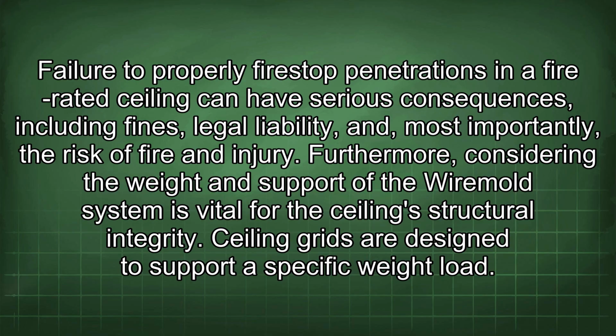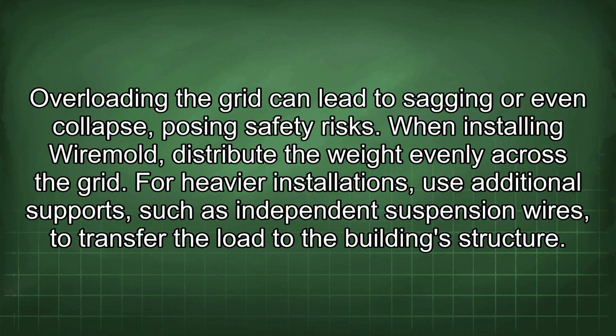Furthermore, considering the weight and support of the Wiremold system is vital for the ceiling's structural integrity. Ceiling grids are designed to support a specific weight load. Overloading the grid can lead to sagging or even collapse, posing safety risks. When installing Wiremold, distribute the weight evenly across the grid. For heavier installations, use additional supports such as independent suspension wires to transfer the load to the building's structure.